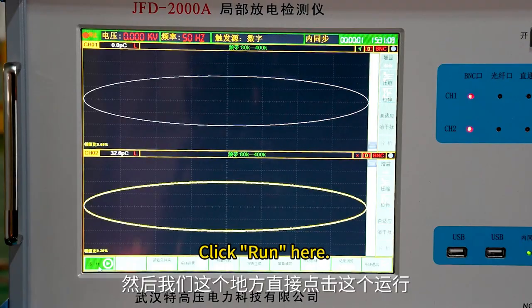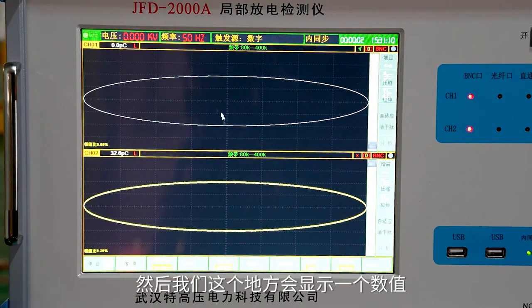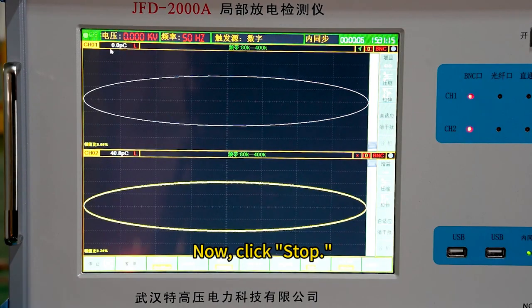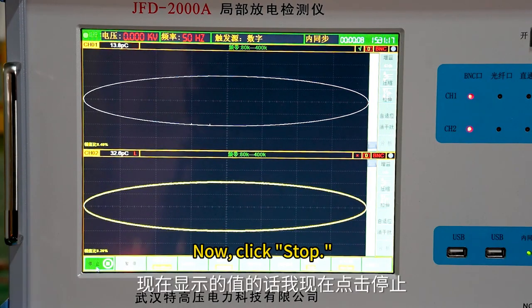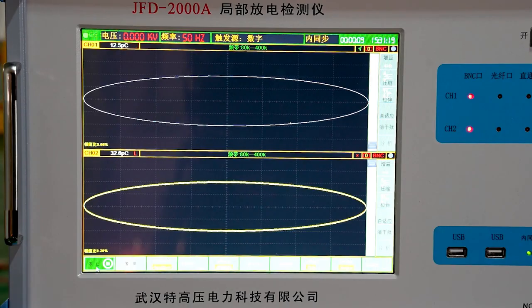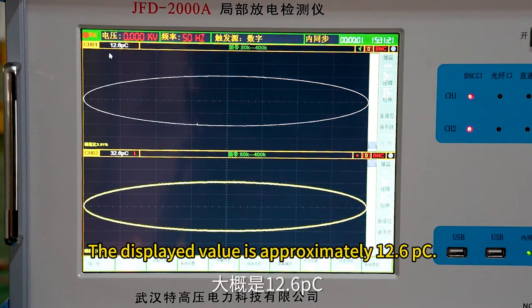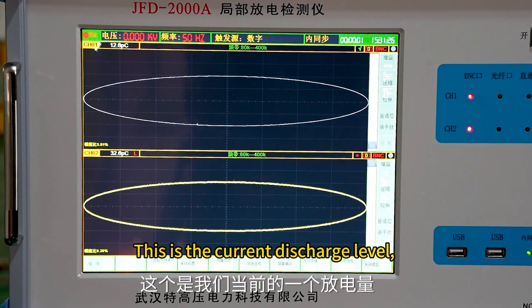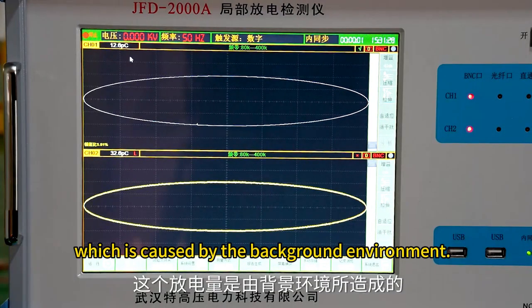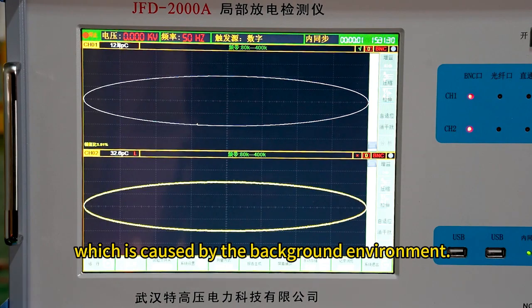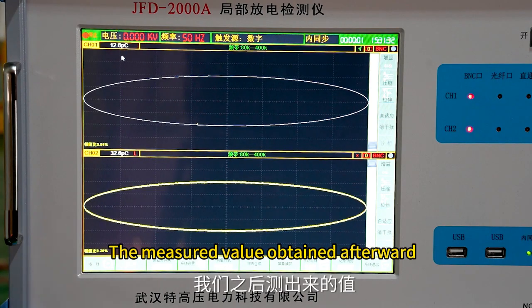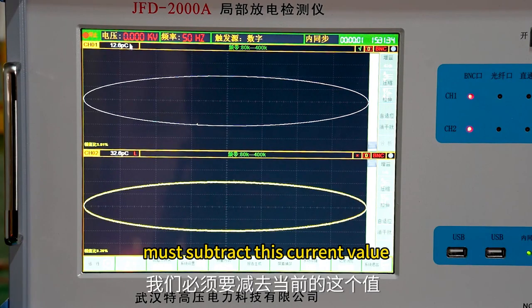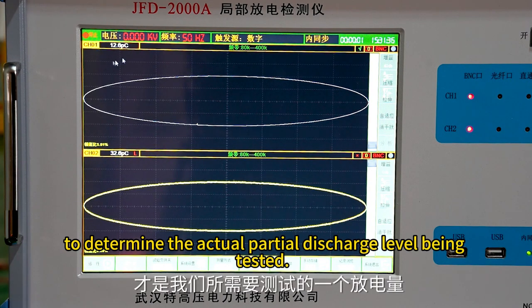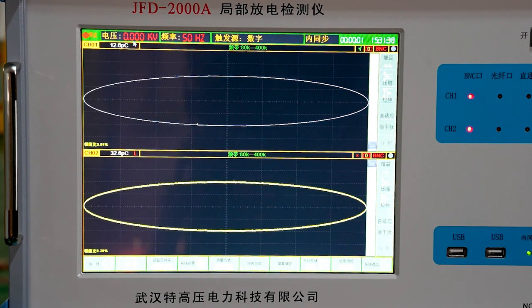Click Run here. A value will be displayed. Now, click Stop. The displayed value is approximately 12.6 pC. This is the current discharge level, which is caused by the background environment. The measured value obtained afterward must subtract this current value to determine the actual partial discharge level being tested.